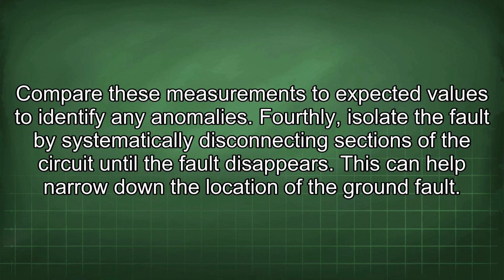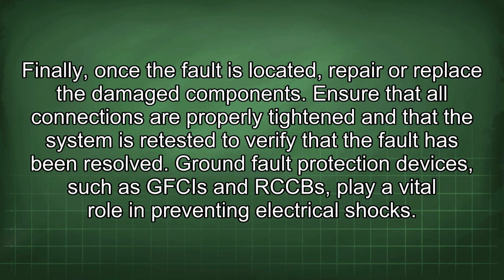Fourthly, isolate the fault by systematically disconnecting sections of the circuit until the fault disappears. This can help narrow down the location of the ground fault. Finally, once the fault is located, repair or replace the damaged components. Ensure that all connections are properly tightened and that the system is retested to verify that the fault has been resolved.